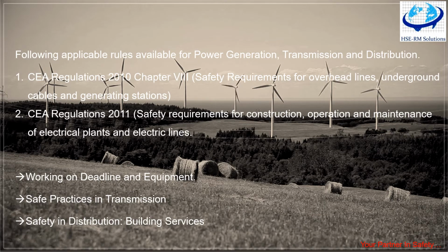The provision for installation and removal of substation equipment should be provided from inside or outside the building without disturbing the associated major equipment in the substation. In places where flooding can occur and the water level may go above 1 meter or 1000 mm, the substation may be located one level above the ground of the utility building. In planning of electrical wiring installation, due consideration shall be made of all the prevailing conditions. All HV cables shall be installed in accordance with good practice.